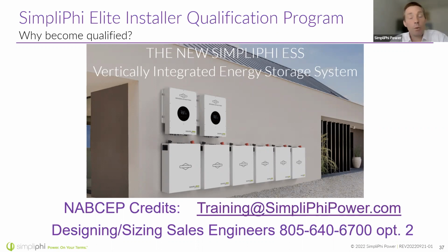Typically, especially with analog BMS units, because there's no communications in there, if the battery is switched off, it only discharges at a rate of about 1% per month. We recommend topping up the battery every 6 months. For example, I spoke with a colleague who had a system fully charged but left sitting in Florida for 1.5 years, and when he checked it, it was still at 94% state of charge. So as long as they're switched off, batteries can sit at low states of charge for longer periods of time.